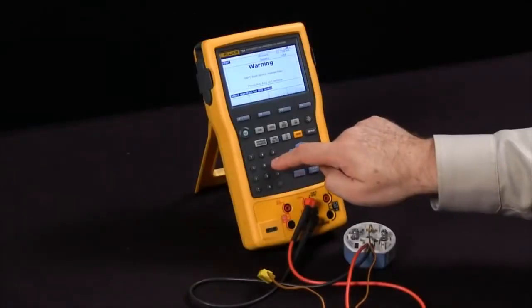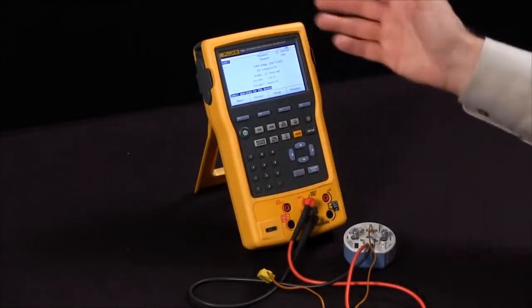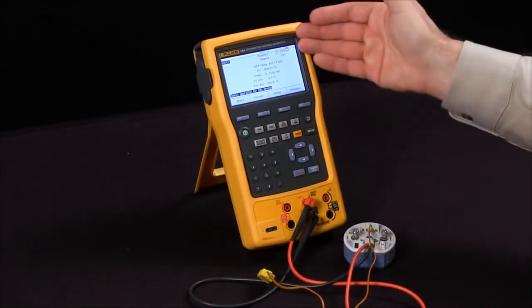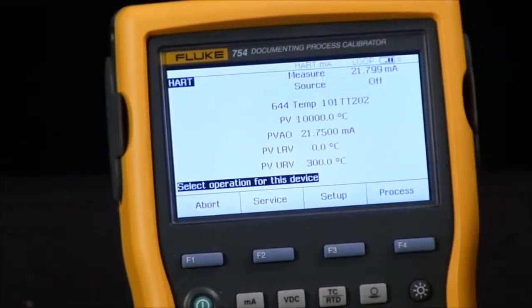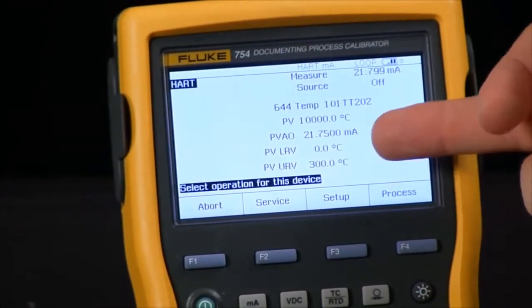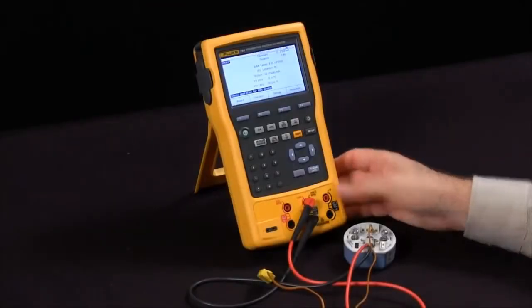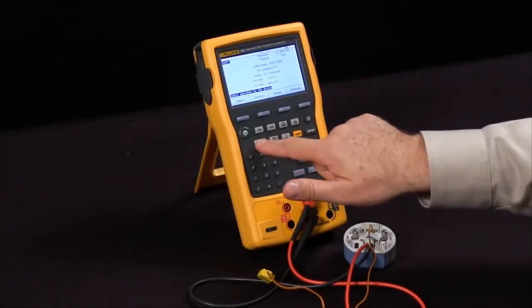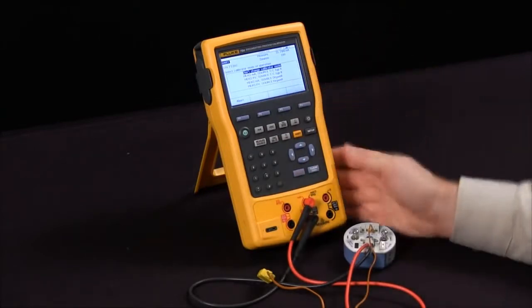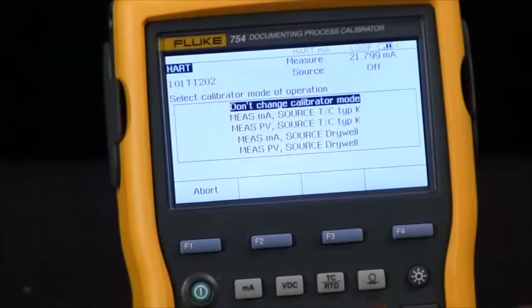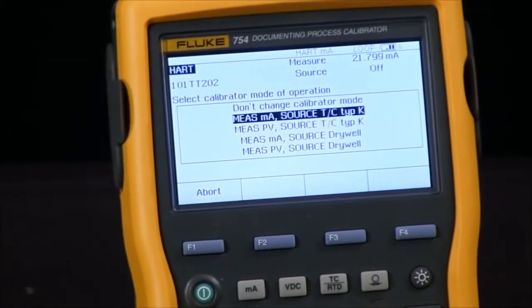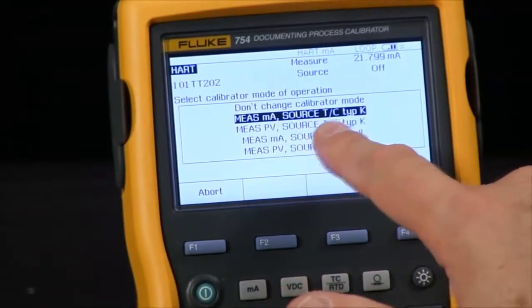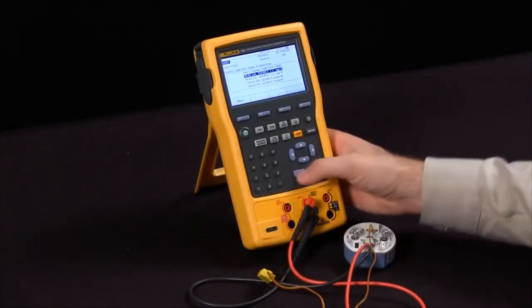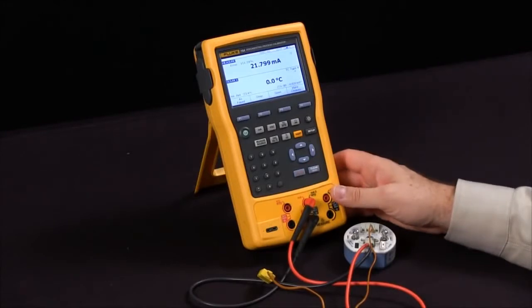It is also letting me know that it is in failure mode right now because we are not sending any signal to it. So we see that it is a temperature transmitter. My lower range value is 0 degrees C. My upper range value is 300 degrees C. I will simply hit the measure and source key, letting the calibrator know what I want it to do. So I will shift down to measure milliamp, and I'm going to source to a thermocouple type K. We're going to enter that.